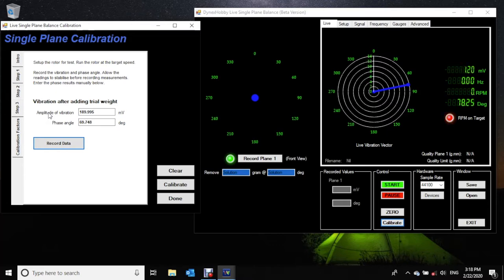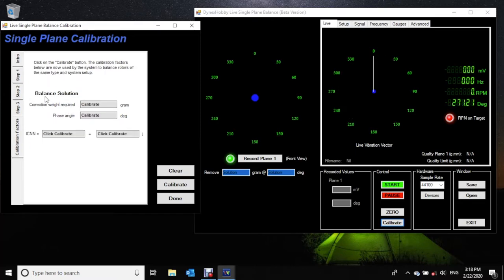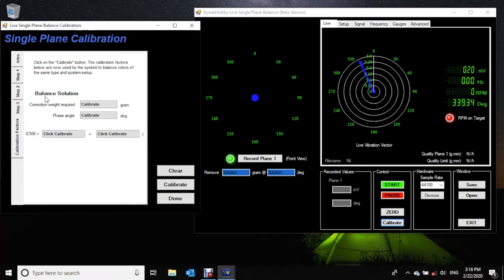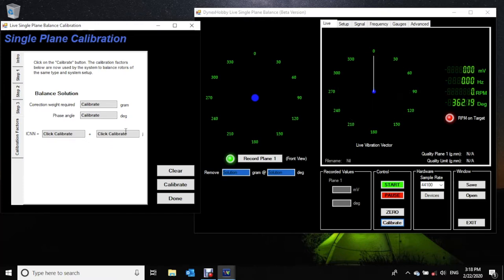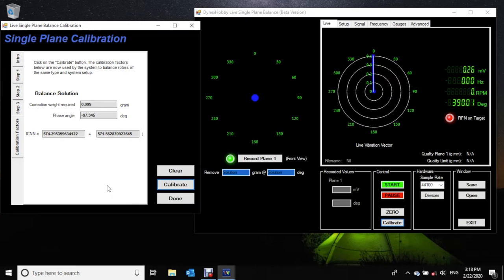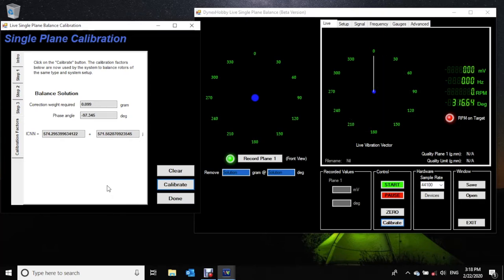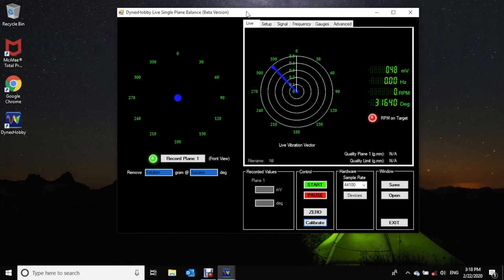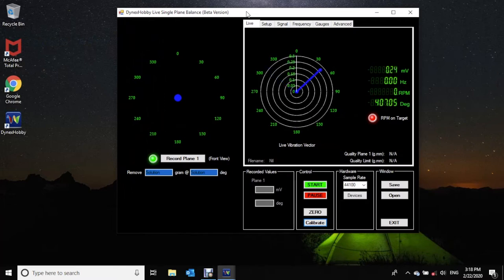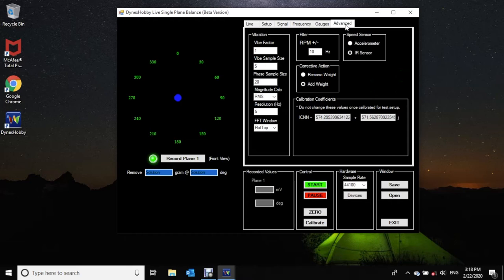Okay, so we've taken the measurement and so we'll switch to the final tab, which is called the calibration factors tab. In the calibration factors tab, we see there's a whole bunch of text boxes there which says click calibrate. So we'll click calibrate and a whole bunch of numbers appear in there. Once that is done, we'll click on done and go back to our main balance window. Now I'm going to switch to the advanced tab, and what you'll notice is that the calibration coefficients have now been transferred to the advanced tab. What these coefficients do is define the mathematical model of the imbalance of the system.